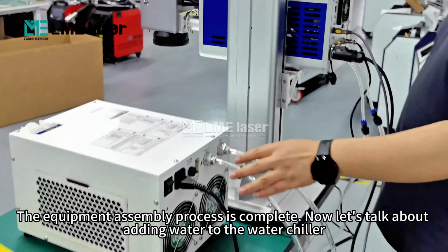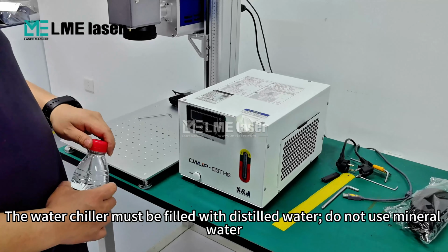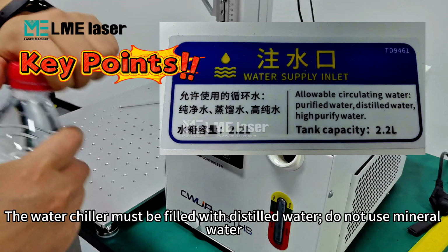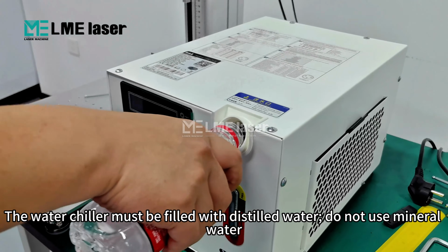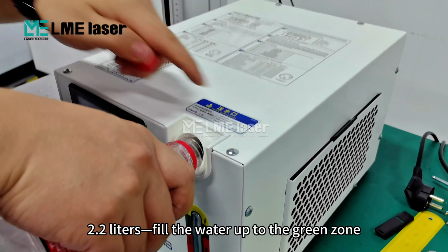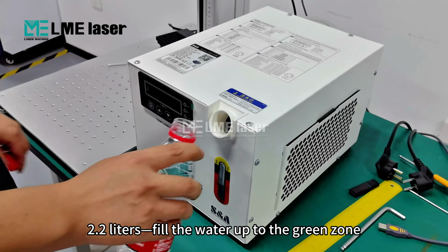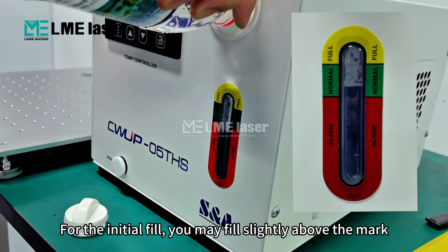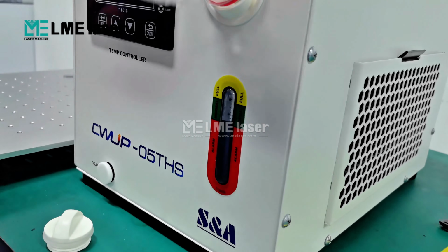Now let's talk about adding water to the water chiller. The water chiller must be filled with distilled water. Do not use mineral water. 2.2 liters fill the water up to the green zone. For the initial fill, you may fill slightly above the mark.